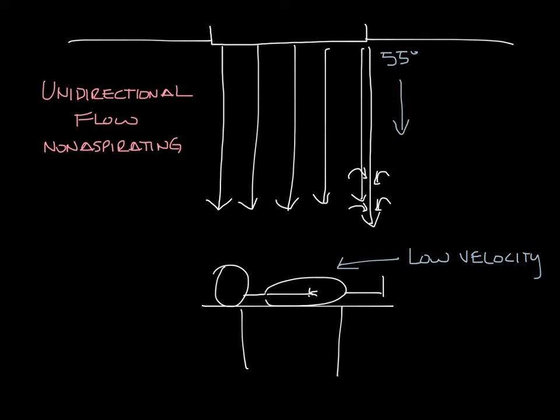This means that it will gain speed as it falls down towards the floor. So it needs to be moving slow enough when it leaves the diffuser face so that it's still moving slowly when it reaches the patient.